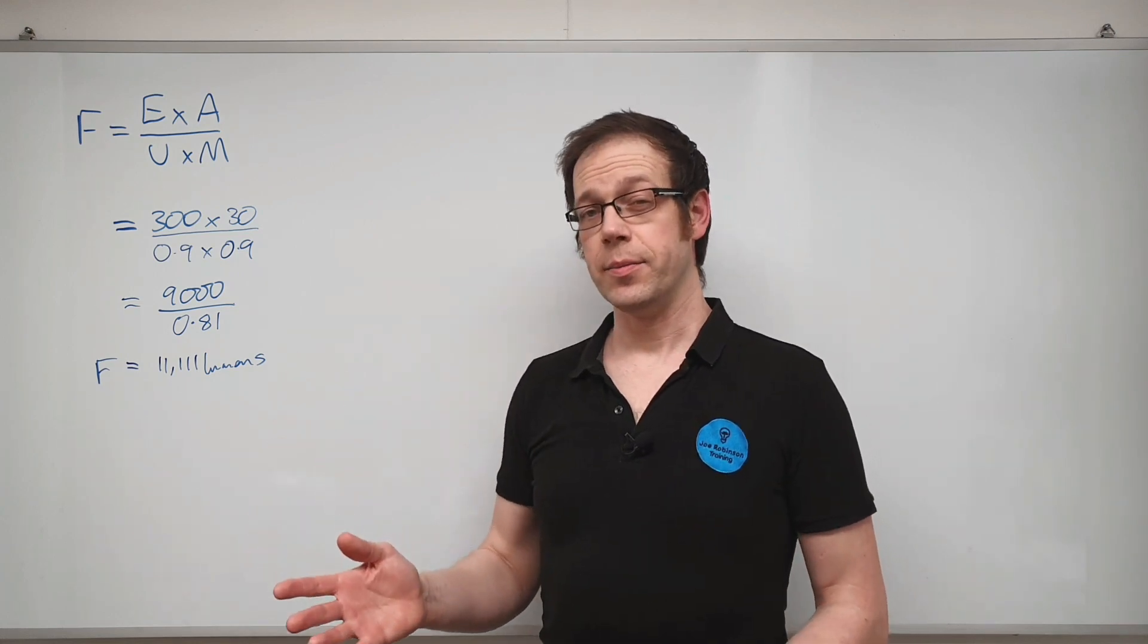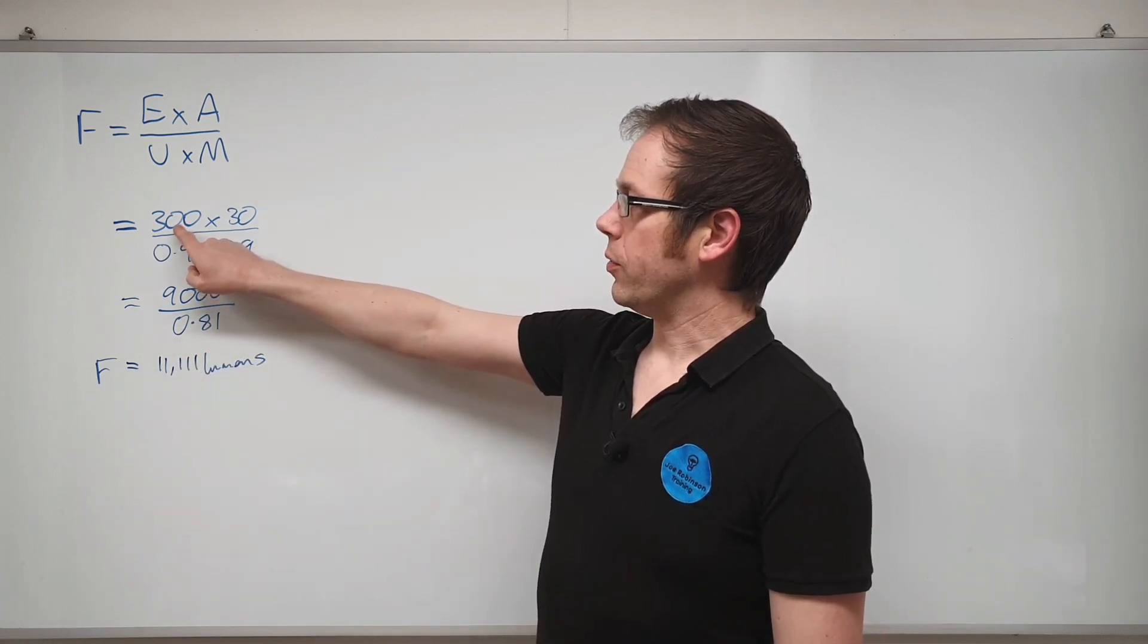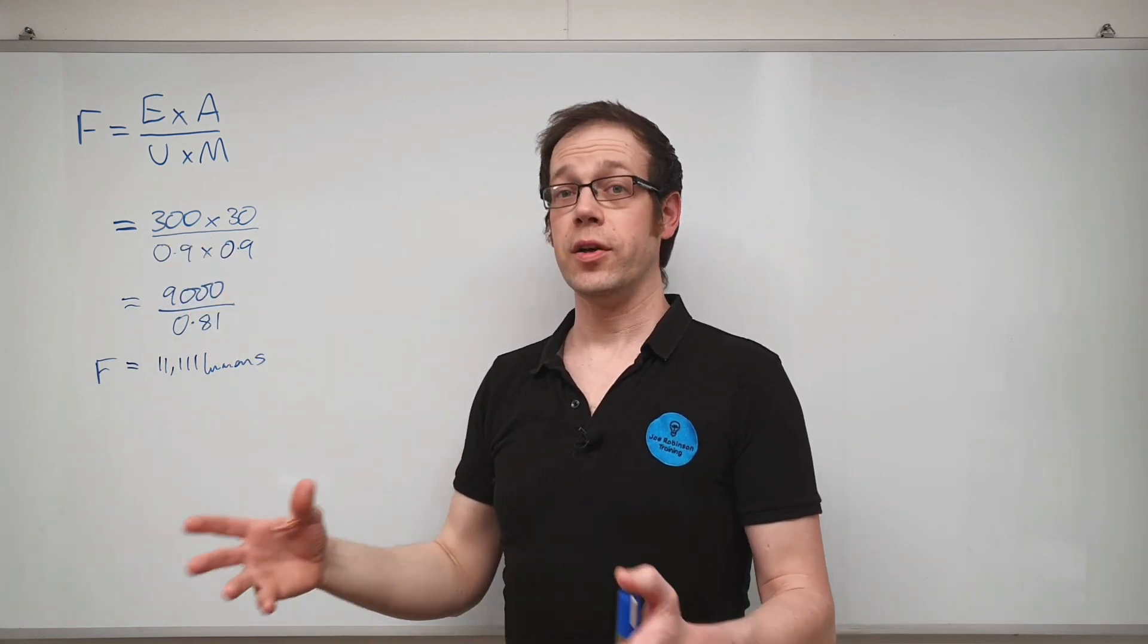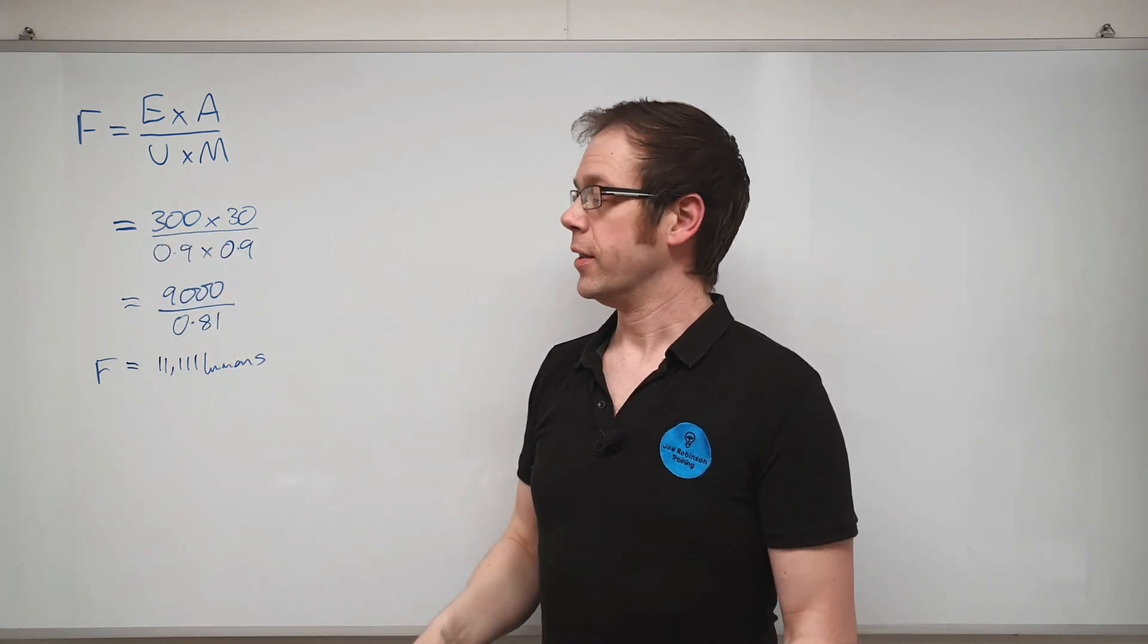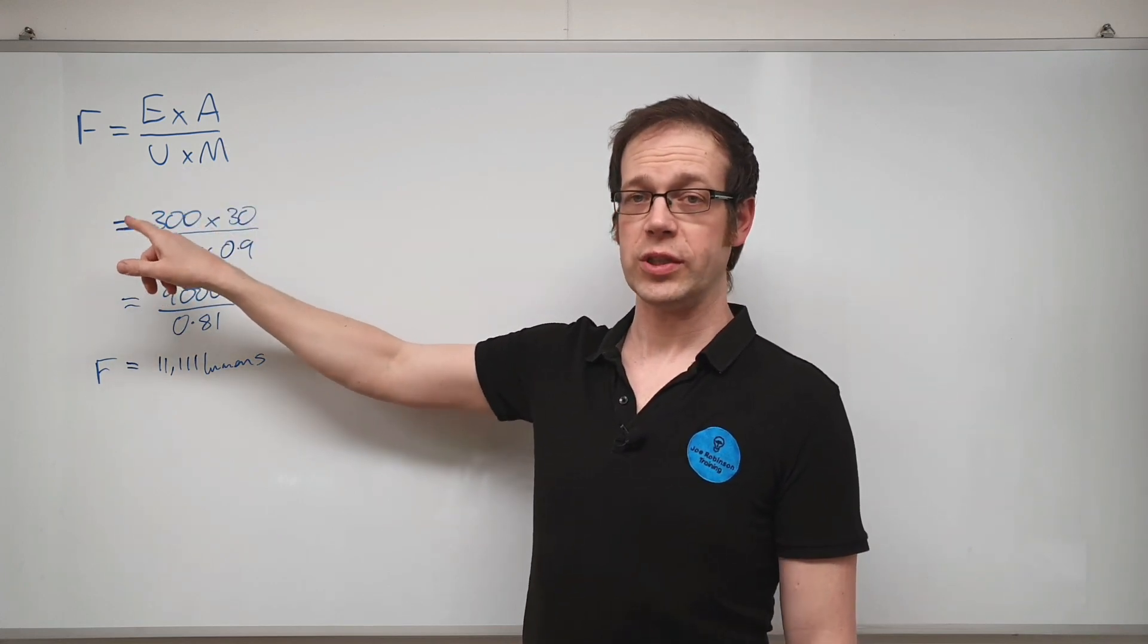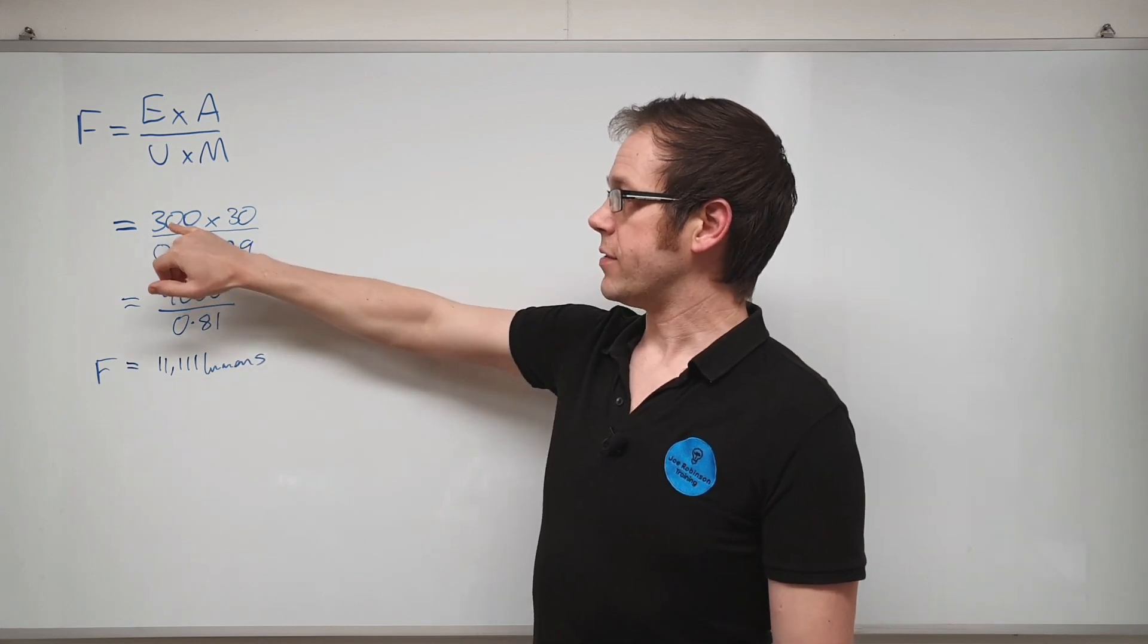Now what starts to happen if you start to juggle with these numbers a little bit? Let's mix it up a little bit. Let's say that we want to make the surfaces brighter, so let's say that the classroom is actually going to be used for night classes. We need to increase the illuminance on those surfaces, so that's now going to be 500 lux, which is a typical value for that kind of application.